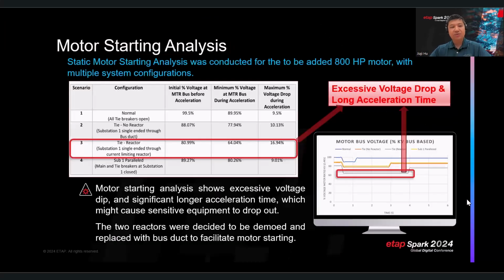So the first step is to do a motor starting analysis. We developed 4 configurations to run a static motor starting analysis. Those configurations would include the first one, the normal configuration. We have all the tie breakers open and all the main breakers closed. This is the ideal configuration that has the best motor starting profile. Then we also have here the substation parallel configuration, which is the two main breakers are closed and also the tie breaker is closed. This is actually a temporary stage that the client doing switching sequence.